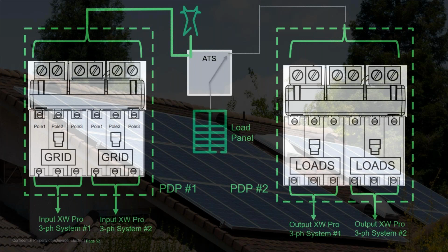When the grid goes down, the external ATS shifts the load to the emergency side of the switch, which is being supplied by the output side of all 6 XW Pro units. The second power distribution panel will house the two additional QOU 360 breakers, which are combined with the second power distribution bar. The 120/208 breaker kit, which is part number 865-1315-01, only ships with 3 QOU 360 breakers. So for this configuration, you will need to source one additional QOU 360 breaker separately.